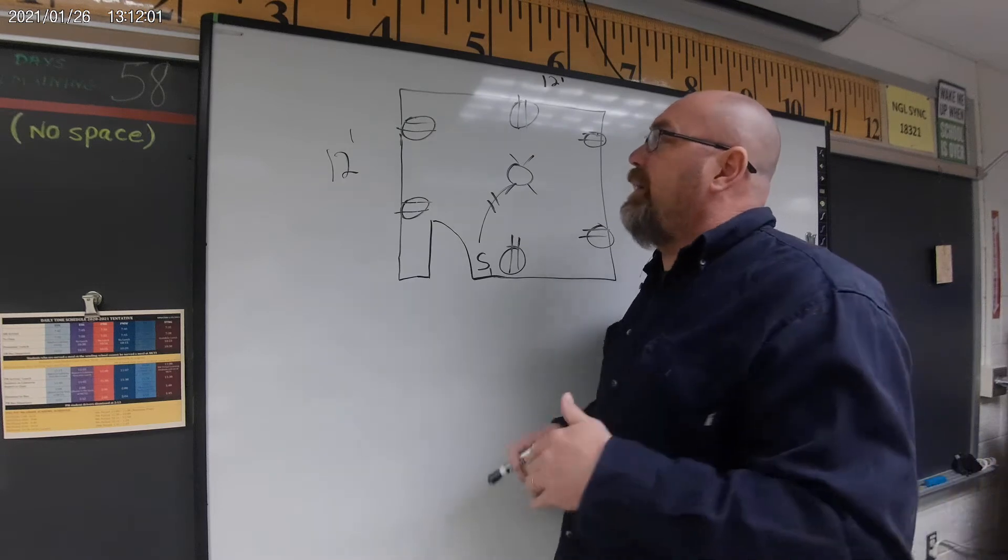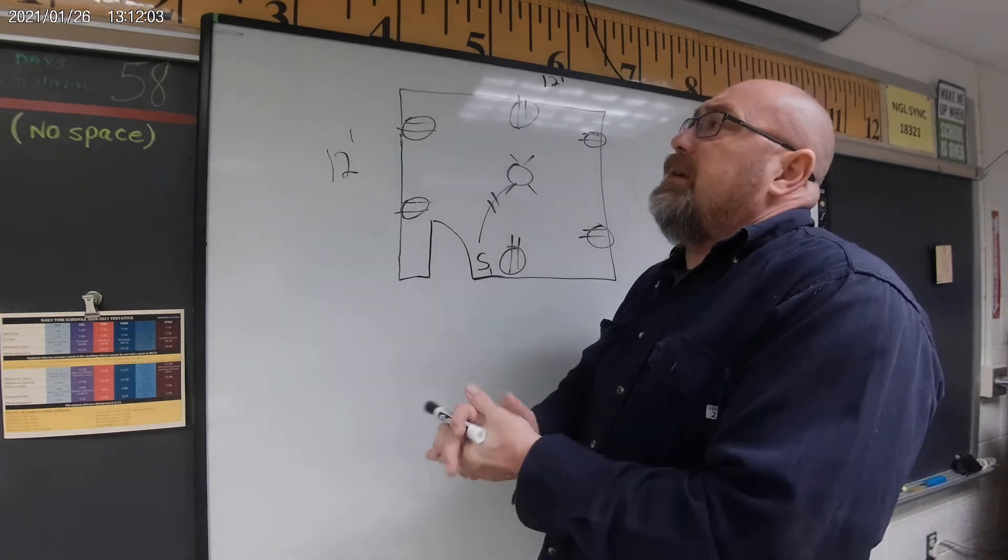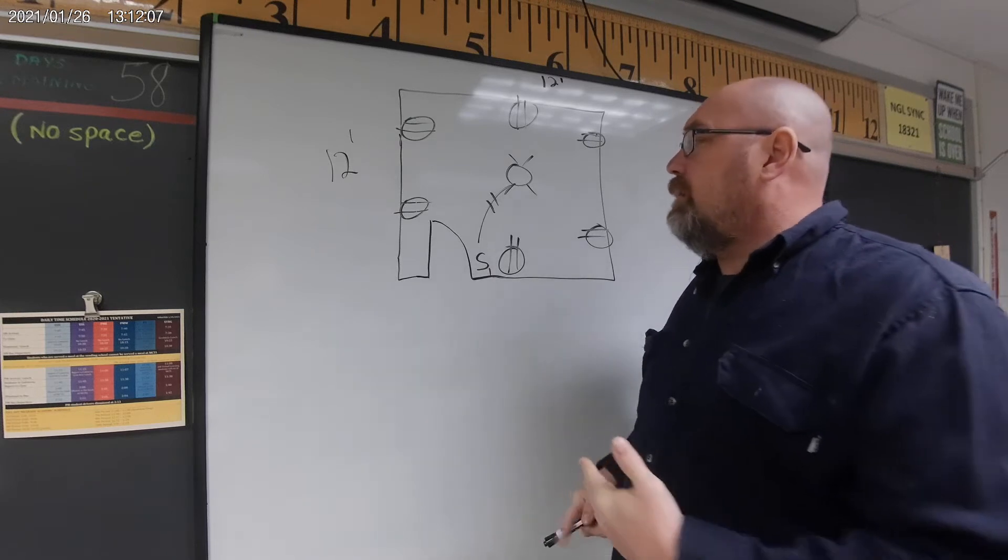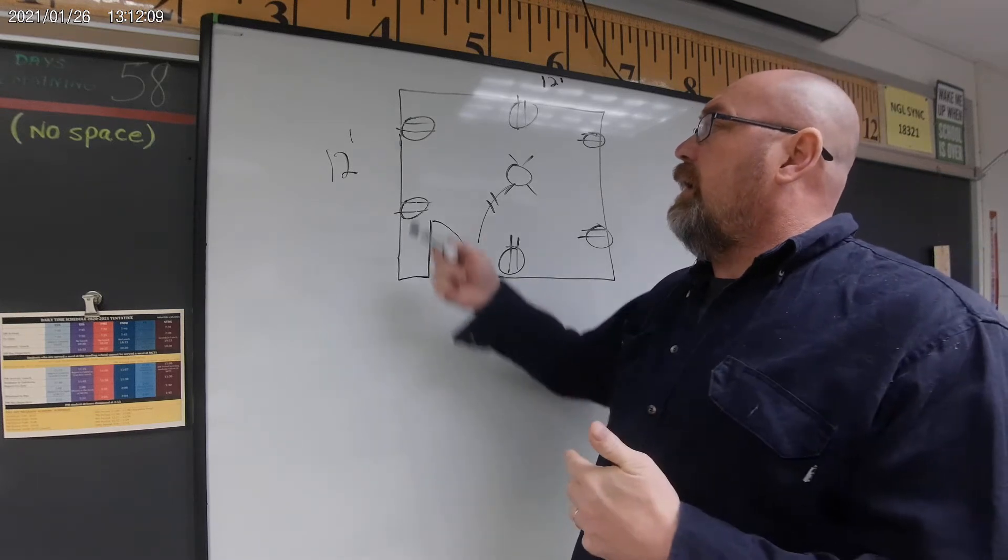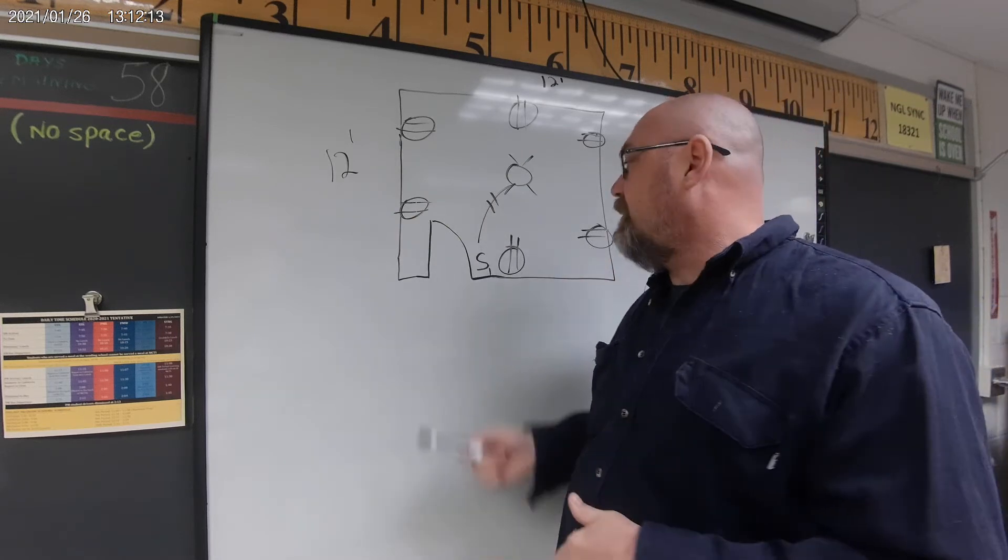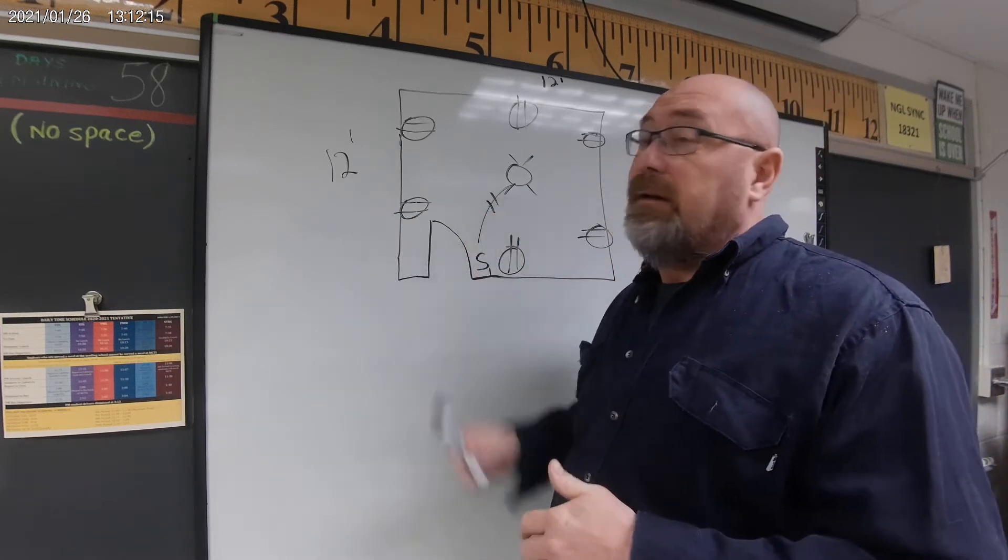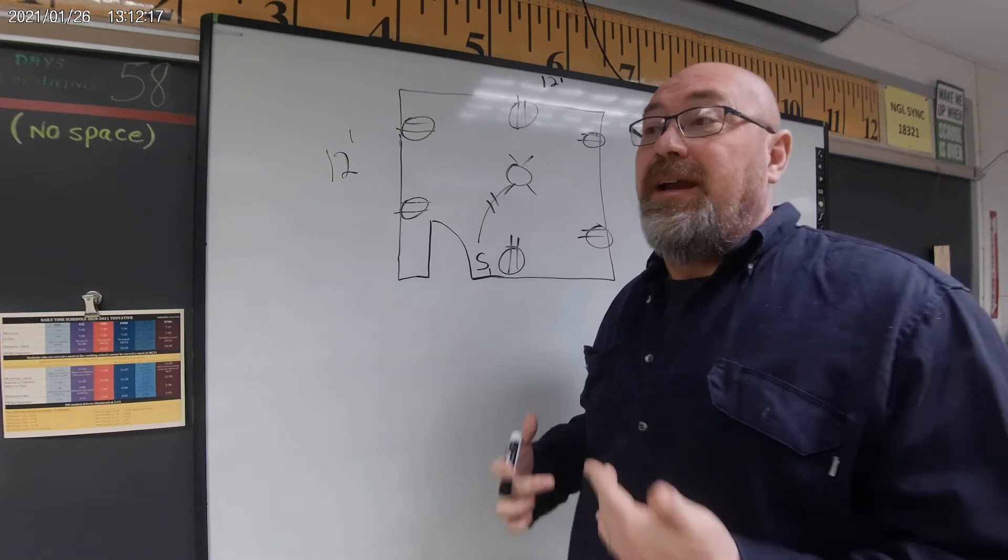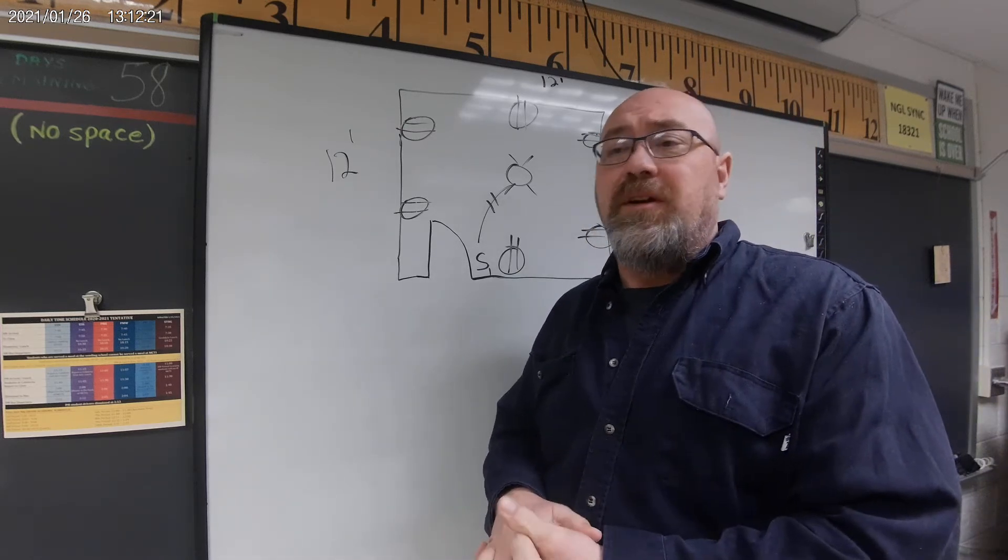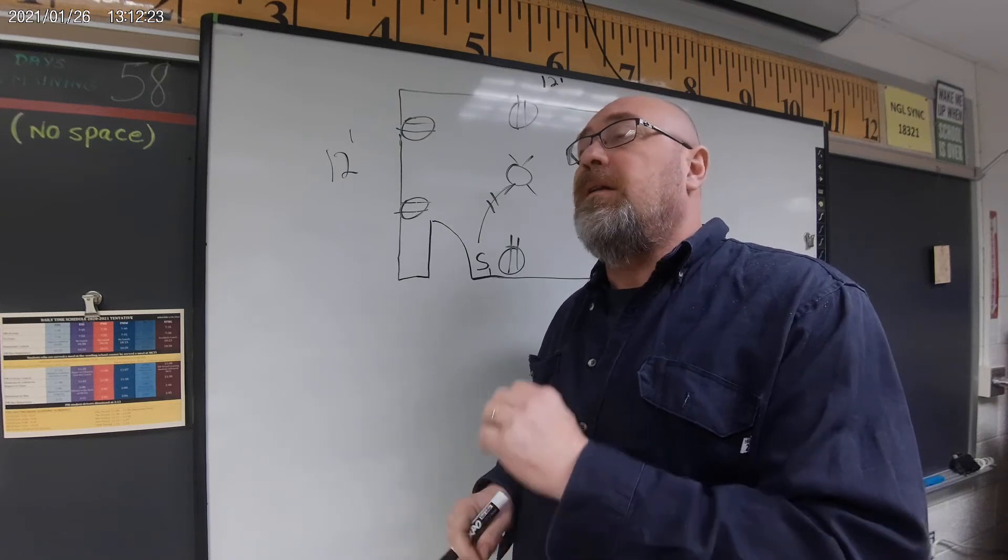Today I'm going to explain how we determine the size of a circuit. Looking at this drawing, I have one, two, three, four, five, six outlets, a switch, and a light—that's eight devices. The code states on a 15 amp circuit, it is preferred that we do not go more than eight devices per circuit.